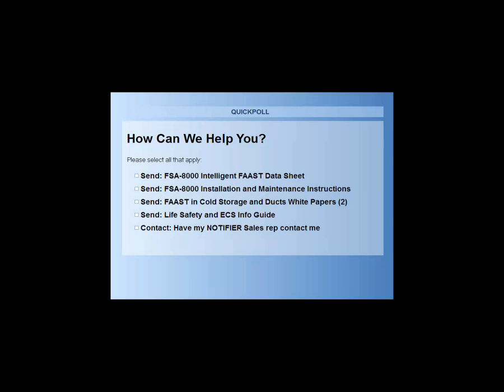But an aspirating detector is flexible enough to be deployed in a residential environment. So when you program the sensitivity thresholds in the FAAST detector, the PipeIQ software will calculate what your effective sensitivity is at each sampling port. As I said earlier in the presentation, each sampling port is looked at the same by NFPA as a spot detector. So when you program the head sensitivity for the FAAST device, in your calculations for the pipe design, it'll tell you what the sensitivity at each hole is. So it could be programmed for normal sensitivity and used in a residential type application, absolutely.